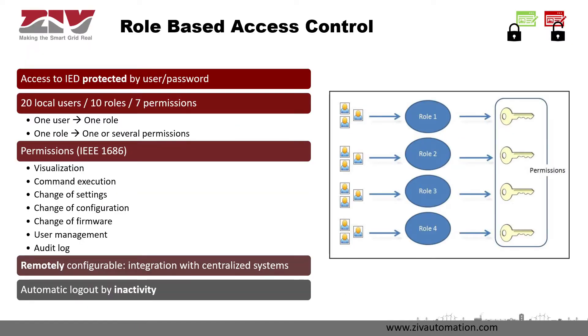One of the main cybersecurity features is securing the access to the IEDs using authentication and authorization, both implemented using role-based access control. Access to the IEDs is protected by a user and password combination, including the local HMI access. The IED has the possibility of defining local users, up to 20, with their passwords.